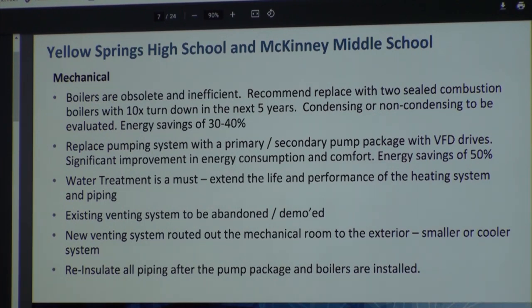So you're paying a lot of money for a high efficiency boiler that's only 5% more efficient, and then you're replacing them every 10 years. The Lochinvar that you have in the middle school are in Mills Lawn - it's a great boiler, they still make that exact model. And that boiler is a high efficient boiler, it's got a 5x turndown. You can buy that boiler in the size you want, and that thing will last 30, 40 years.